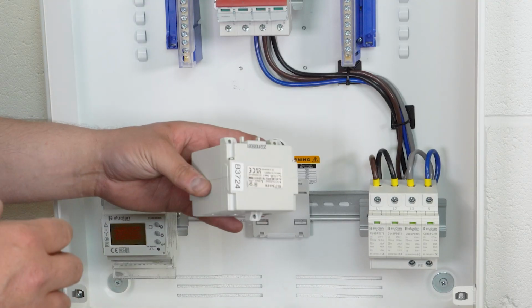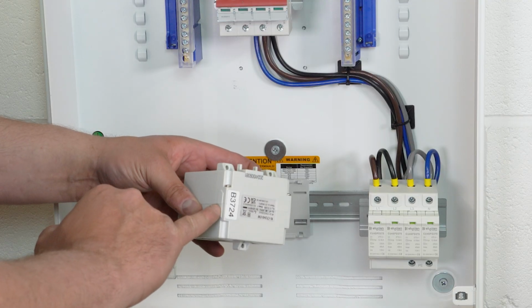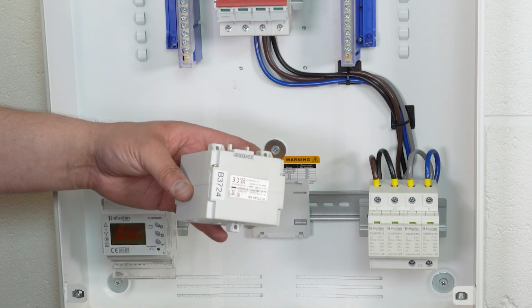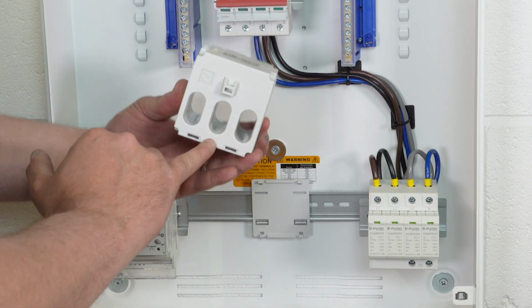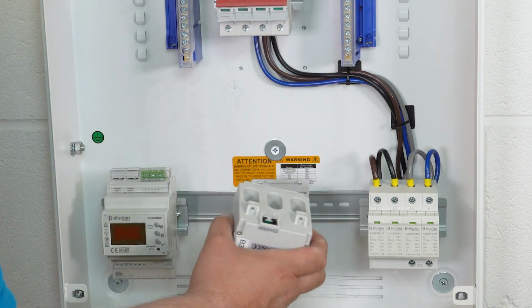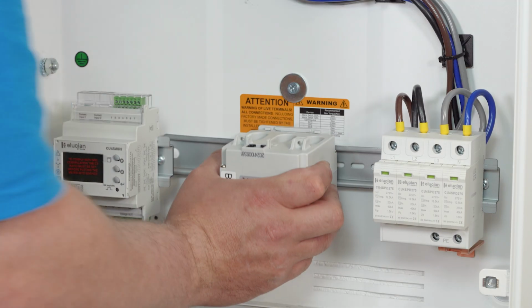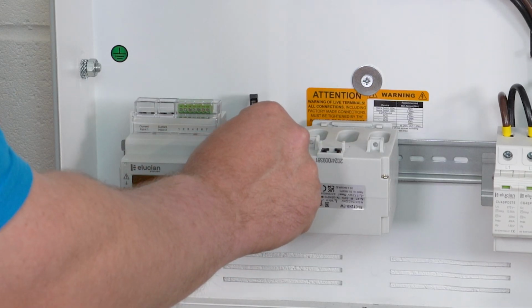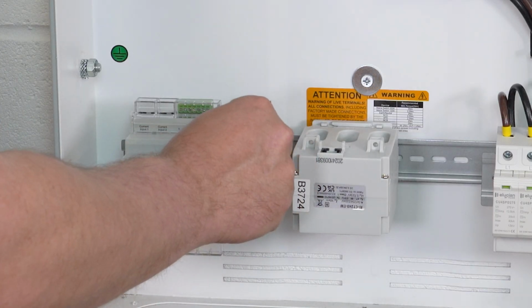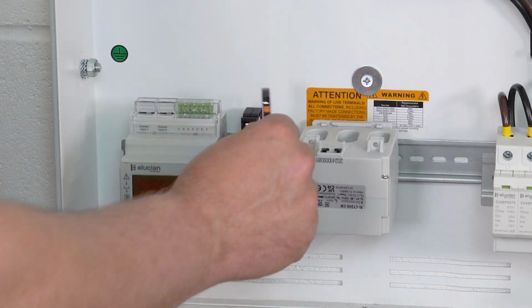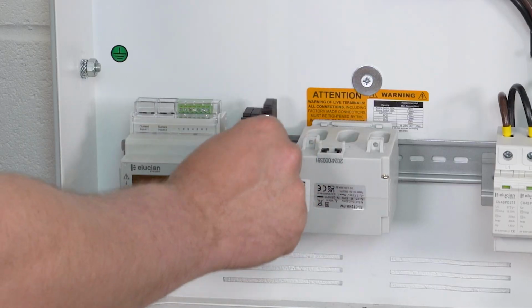On the 125 amp current transformer, ensure the arrow faces upwards or P1 faces down towards the incoming power supply for correct fixing. Clip the current transformer onto the mounting bracket. Attach the fuses to the DIN rail beside the energy meter. Please note that the fuses are not supplied with the kit and will need to be obtained separately.